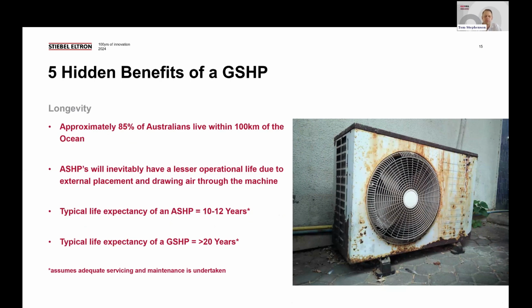Air source units will inevitably have a lesser operational life due to external placement and the need to draw air through the unit, particularly right on the coast, where consumers generally have higher heat loads and cooling loads because of the nature of their builds, needing a greater volume of HVAC equipment and a higher capital cost. So we'd budget consumers on a typical life expectancy of an air source heat pump of somewhere between 10 to 12 years, sometimes less in a critical coastal climate like the right-hand picture. A ground source heat pump, if well maintained, can last greater than 20 years.